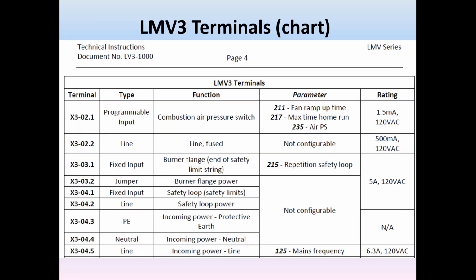The LMV3, starting on page 4, has a chart that shows an extensive listing of every single terminal on the LMV3 and the AGM60. It includes a terminal number, in this case 321. This particular terminal has a type. It is programmable. Its function is the air pressure switch. And the parameters, like 211, gives you time setting to make the air pressure switch.